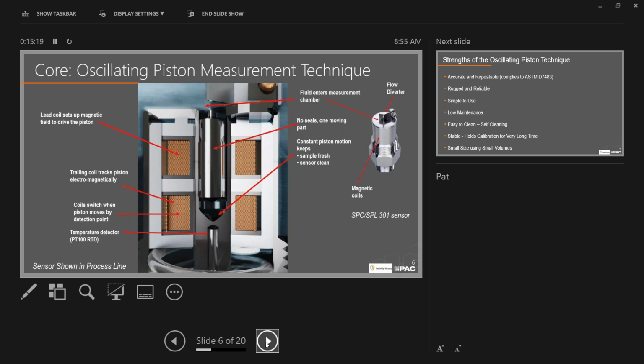So something else I'd just like to highlight is the simplicity of the device and how rugged it is. This is basically a stainless steel cylinder where the piston is traveling. It's welded closed at the bottom, and it's open to the process at the top. And it's wrapped in copper coils that are wrapped in another layer of 316 stainless steel. So this is rugged. There's nothing to break. This can be dropped, and that's not going to hurt it, and it won't affect the calibration. So it is a very reliable piece of equipment to have in your plant.